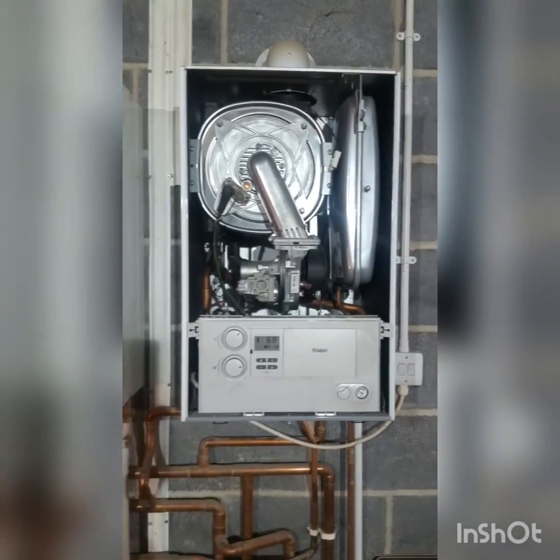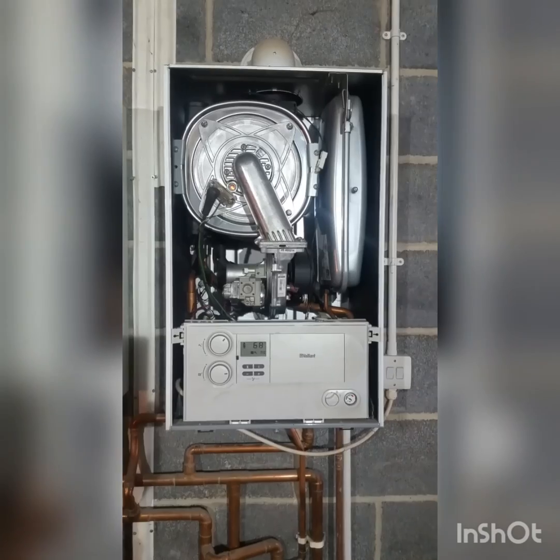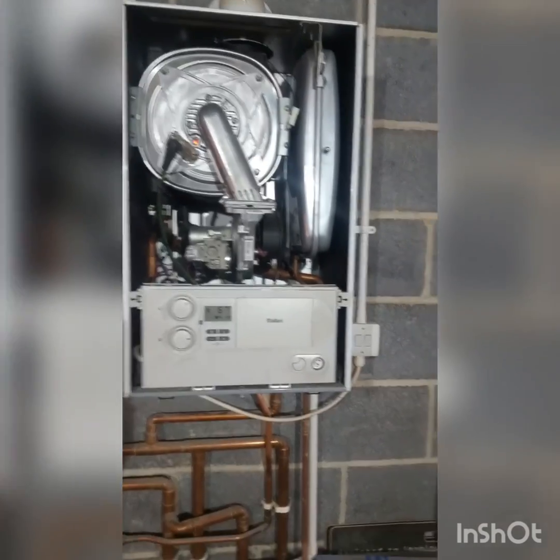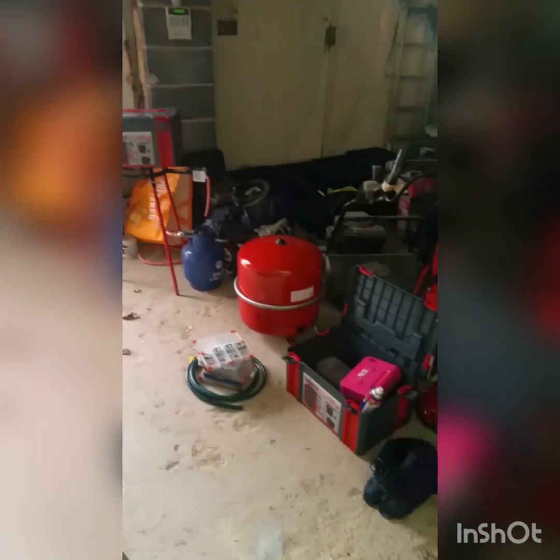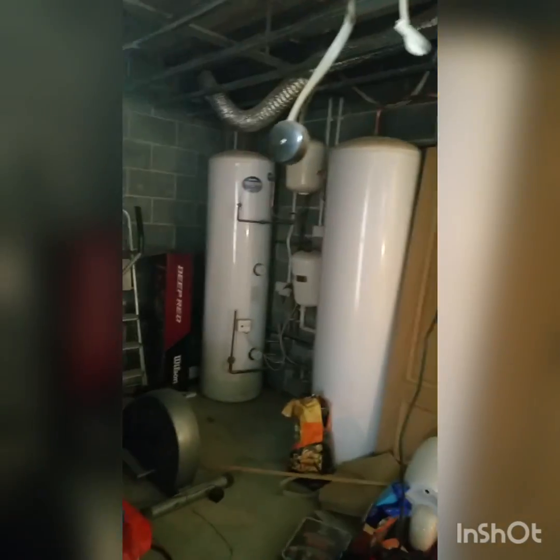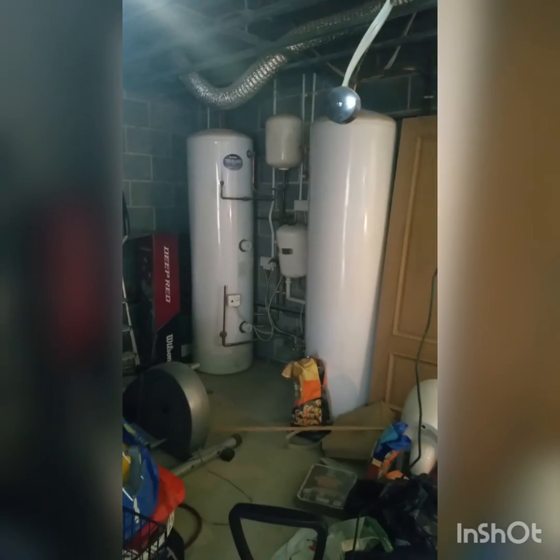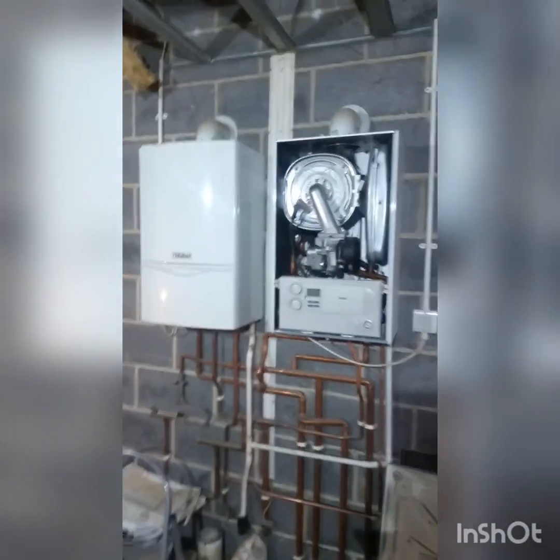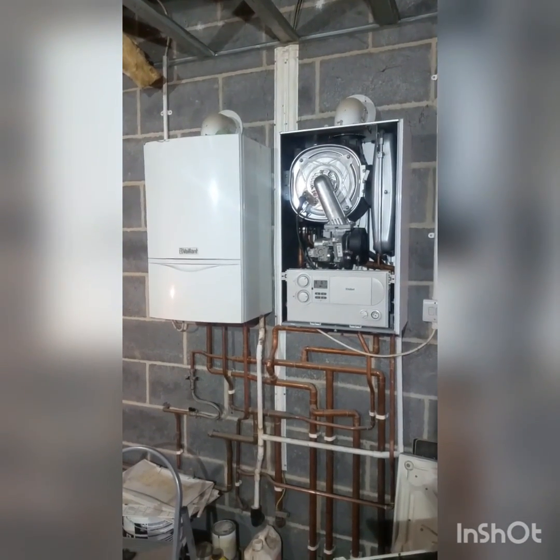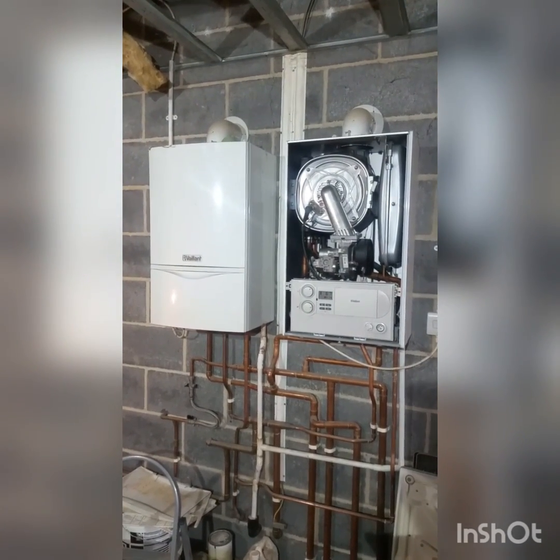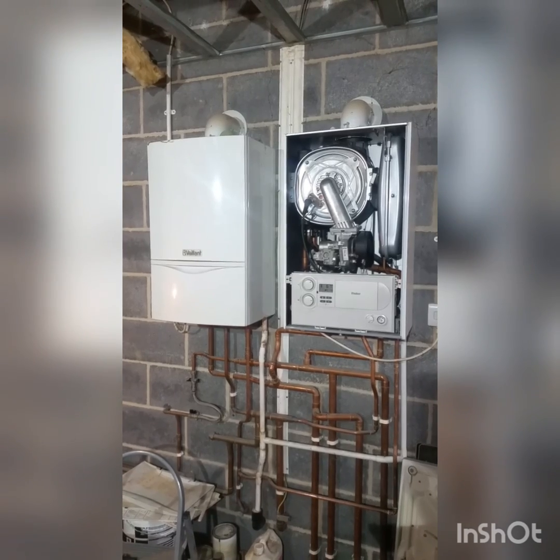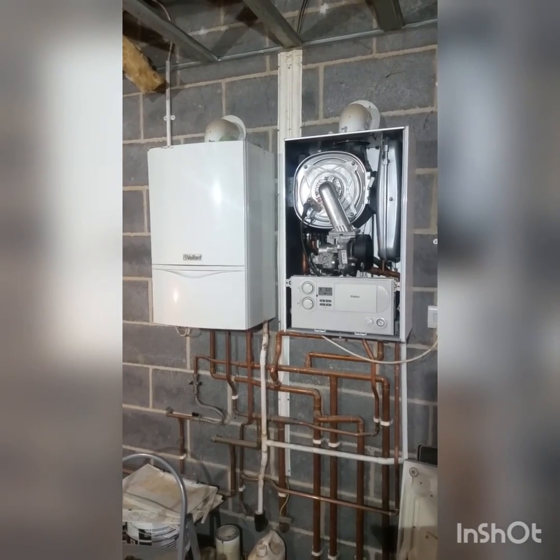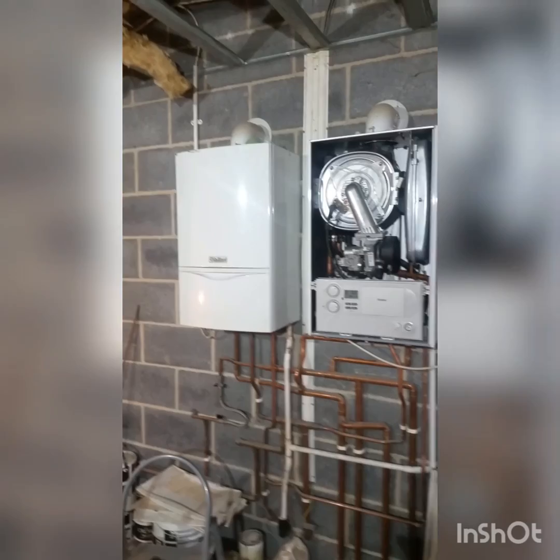Also, big house, and it's only got the internal expansion vessels on the boiler, no additional expansion vessels. So over here I've got a nice big one that I'm going to be putting in later on. It's running 2 unvented cylinders, and I'm not sure what to do about the control concept. Basically, if I get the VRC 700, I believe that works like a boiler controller, and will run the 2 boilers as a tandem pair, and give me weather compensation.